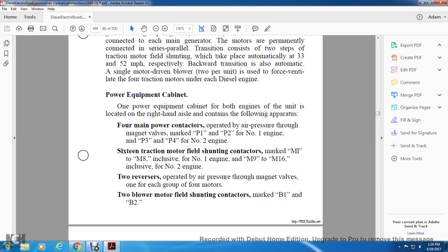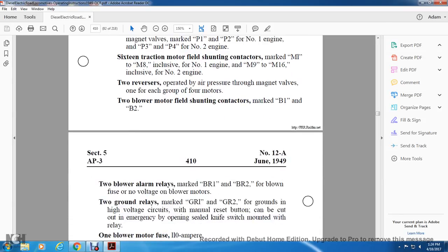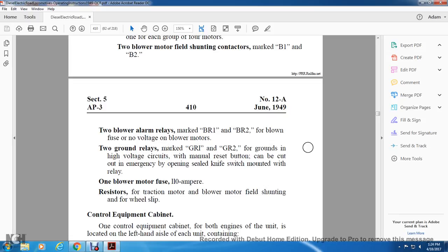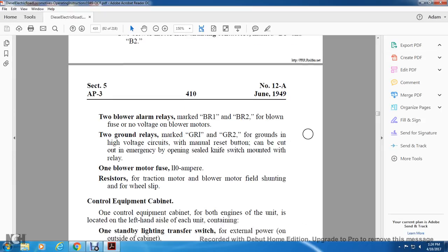2 reversers operated with air pressure through the magnet valve, one for each group of 4 motors. 2 blower motor field shunting contactors marked B1 and B2. Two blower alarm relays marked BR1 and BR2 for a blown fuse or no voltage at the blower motors. Two ground relays marked GR1 and GR2 for grounds in the high voltage circuits. The manual reset button can be cut out, and there is an emergency open with a sealed knife switch mounted with the relay. One blower motor fuse is 110 amperes. Resistor of the traction motor and blower motor field shunting with the wheel slip.